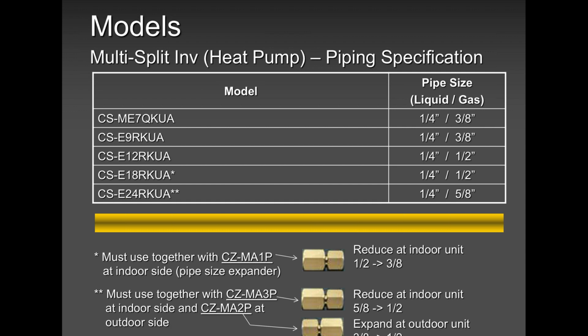So please, our outdoor unit has 2 size ports on all the zones, whether it's a 2, 3, 4 or a 5 zone, all have 3/8 and quarter, 3/8 and quarter. 3/8 suction, 1/4 inch liquid, 3/8 suction, 1/4 inch liquid. And if you have a 12,000 or an 18,000 that uses 1/2 inch, run the 3/8 and the 1/4 from the outdoor unit all the way to the indoor unit. And when you get to the indoor unit, buy one of these adapters that converts from 3/8 to 1/2 inch and use it at the indoor head.